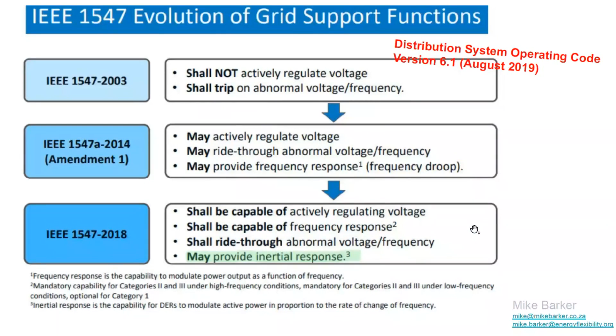So another way to look at it is 1547 is not just one standard, it's a number of standards, starting with 1547.1, a set of test procedures for conformance, all the way through to the UL guys jumping in with a certification approach. You can actually go out and buy 1547 compliant devices, from China, a lot from America, and some from Europe—they're widely available. If you dig into the specs you might find reference to UL 1741 as well, that's the certification.